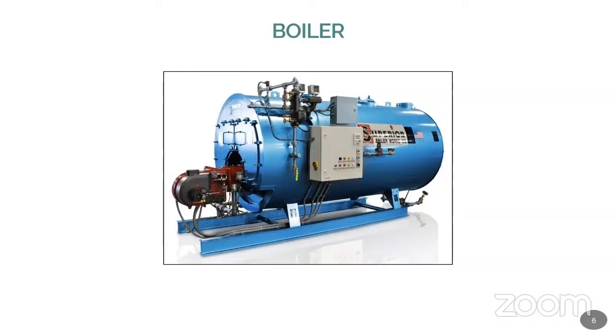Okay. Now let us assume that I produce the steam and transfer it from the boiler to the process through a piping system. Now the process is using my steam. After using my steam, the process is completed. Then what about the steam? What will happen to the steam after usage? When the steam is used completely, automatically it starts to condense. Am I correct? Because you have taken the energy available in the steam for the process application. When you take the energy away, it goes from gas back to water, whereas giving energy takes it from water to gas. So if you take the energy, it comes back to its original state, that means from gas to water. That is called condensate. Okay, so it starts to condense.